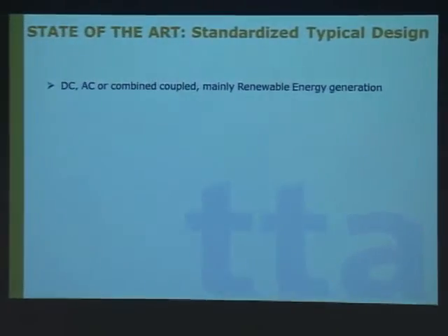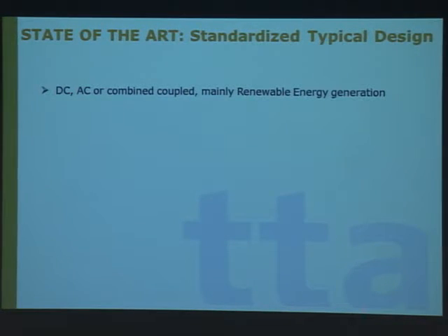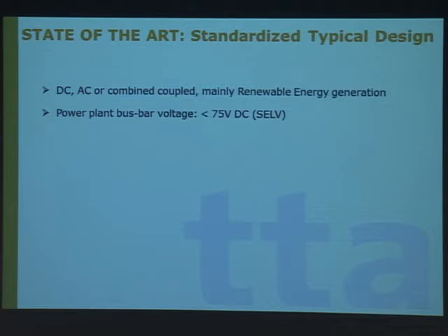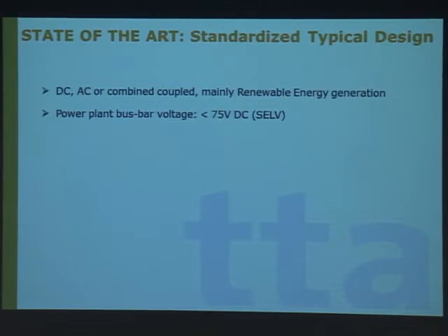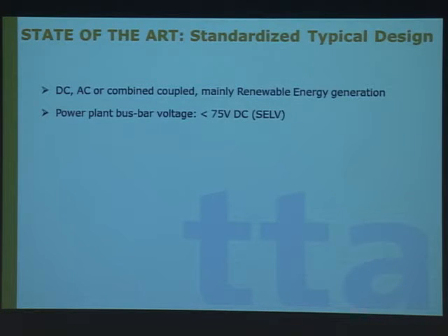So, as I said, other aspects include this DC or AC or combined coupling, and decision on the voltage. You'll see that many batteries can operate at low voltage, up to here it's up to 600 volts, in Europe up to 1000 volts, but we try to stay below what is called extra low safety voltage, which in Europe is less than 75 volts. I think in North America it's 100 or 110, because you always end up with the risk that an unqualified technician tries to play with the DC bus and the batteries in these rural settings.